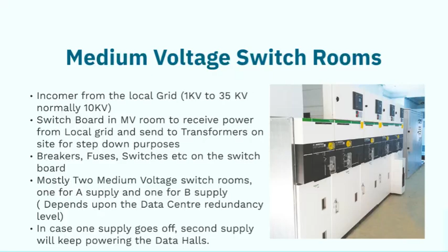Mostly two medium voltage switch rooms, one for A supply and one for B supply. It all depends upon the data center redundancy level, which I've explained in my previous lecture and will explain in detail in my next lectures as well. So in a medium voltage switch room, we receive medium voltage from the national grid, then send it to the transformers.